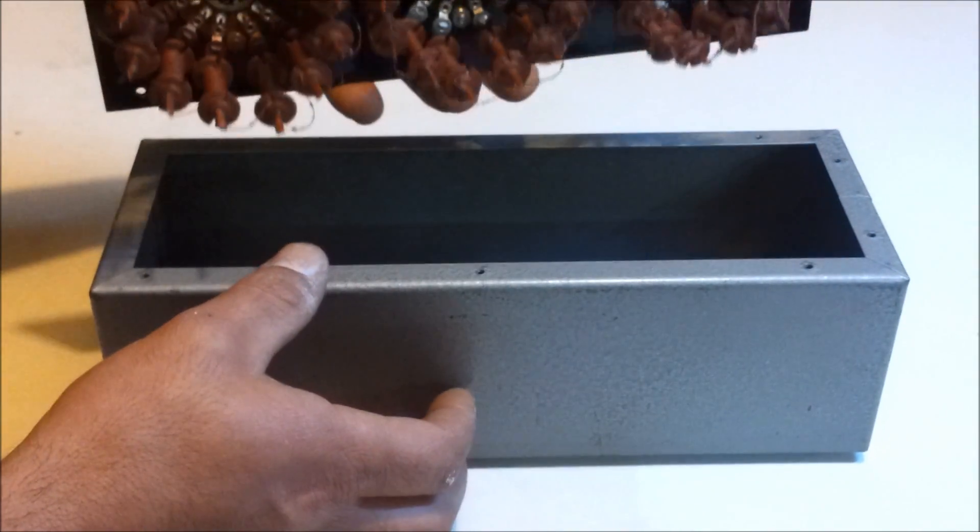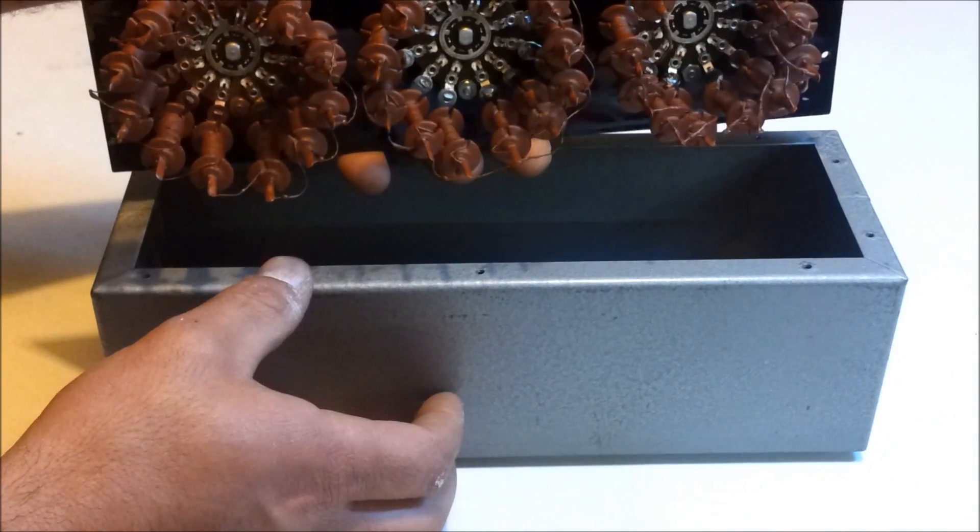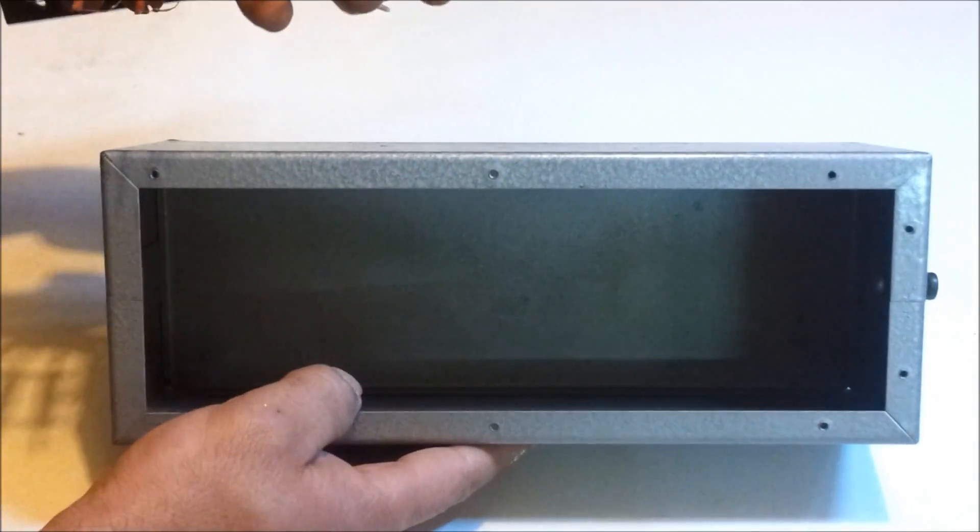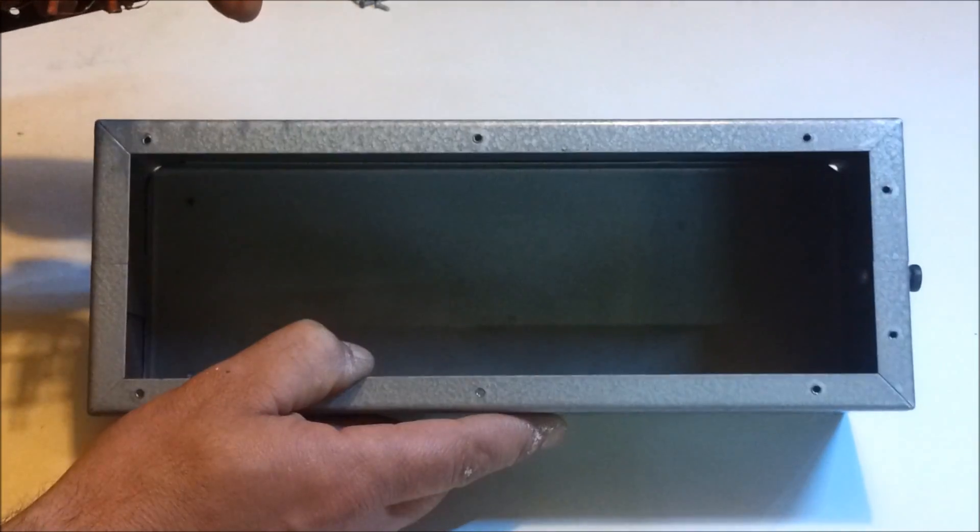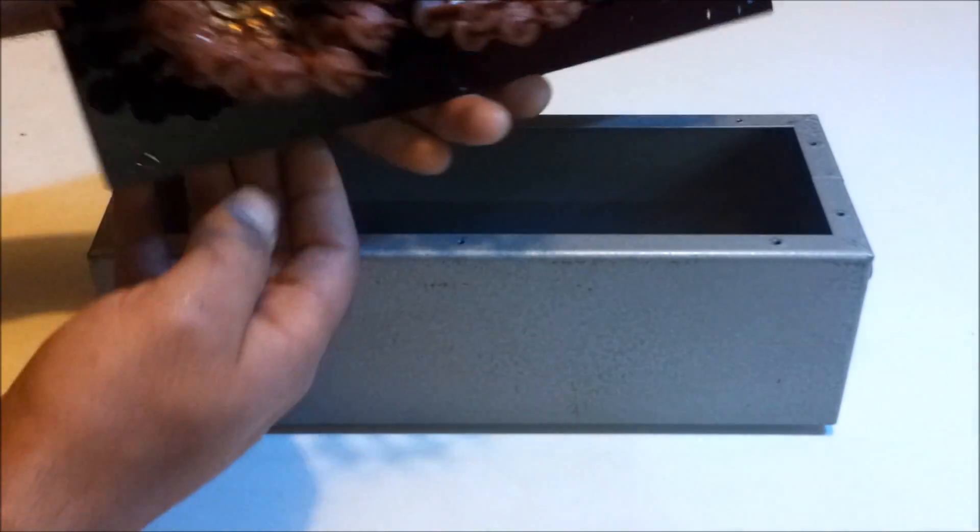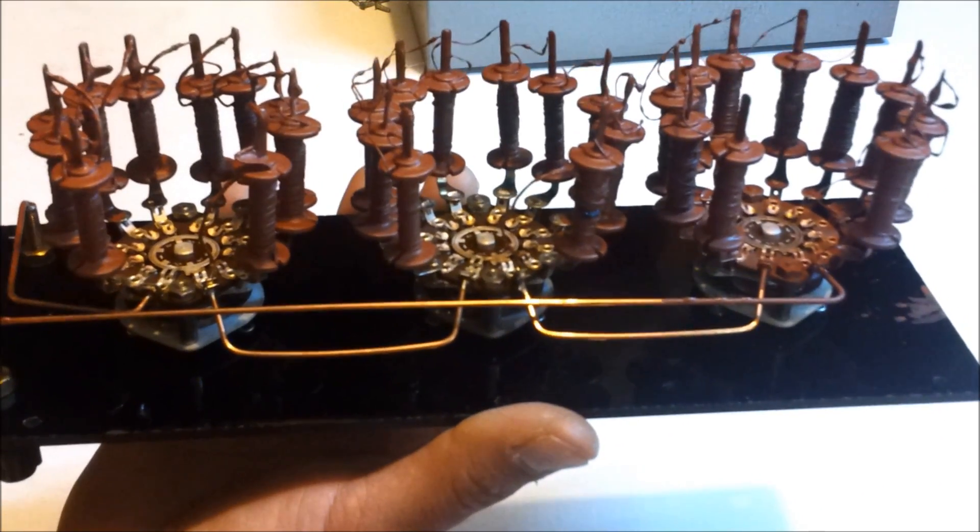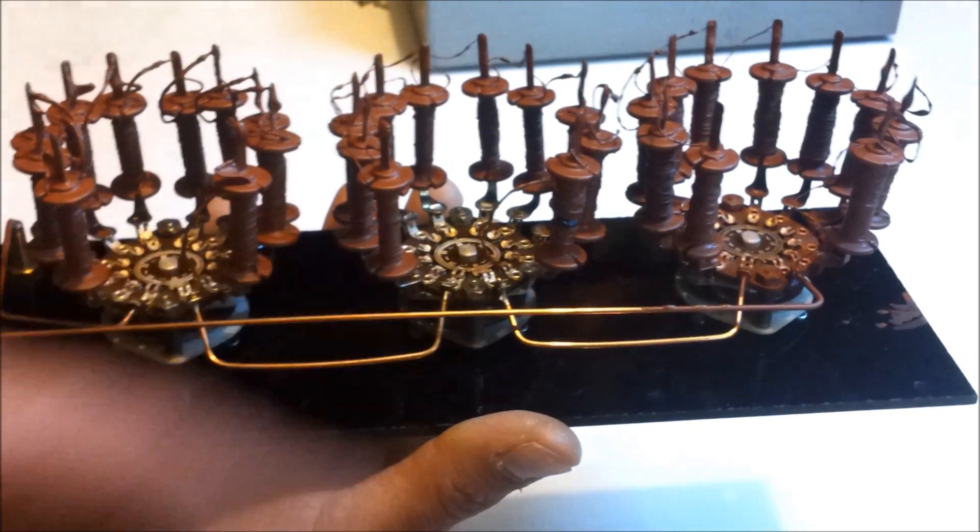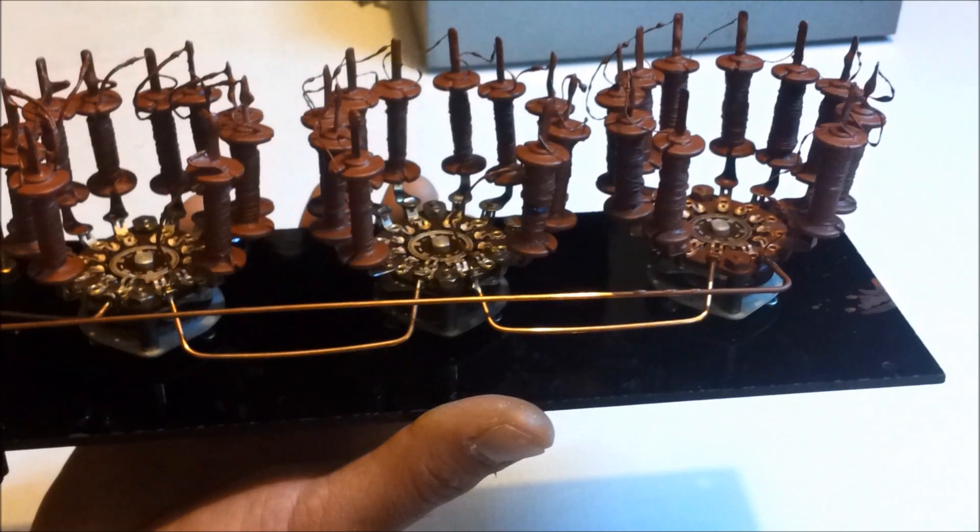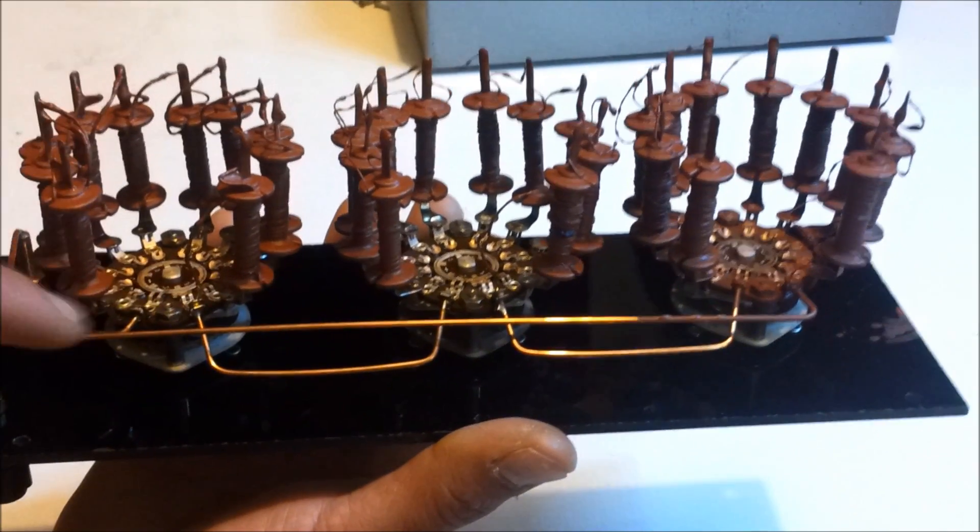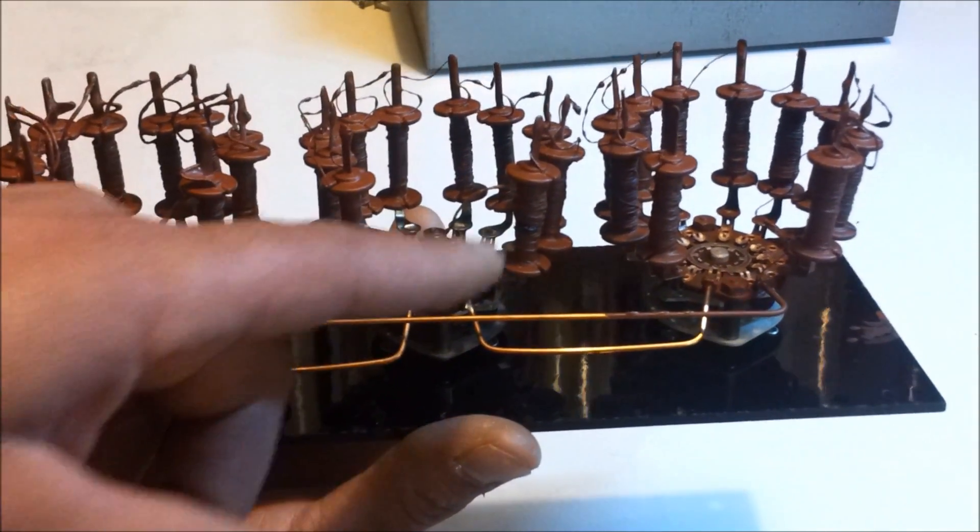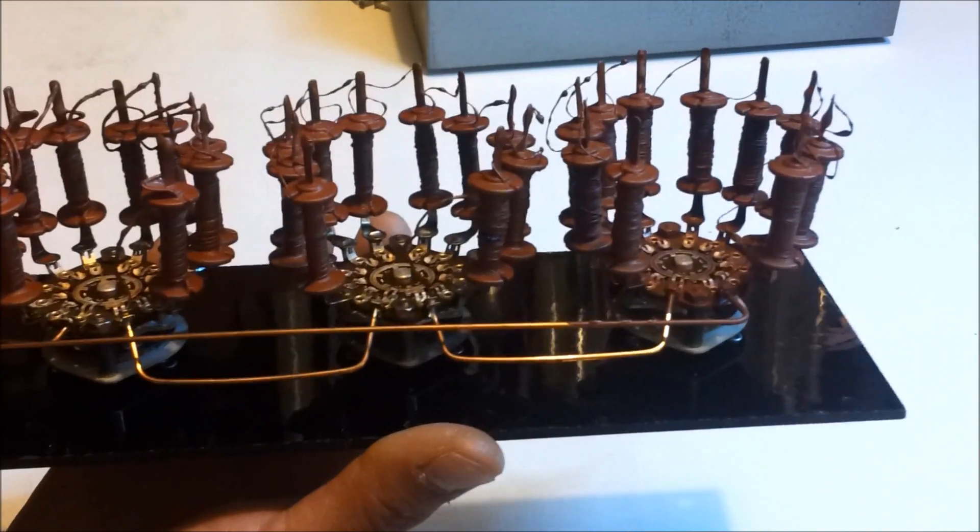That is pretty funky, pretty old-school looking. As you can see, the inside of the box is just a bit of folded steel, but this is where all the magic happens. We've got these solid copper bars here connecting the rotary switches together, and each one just contains wire wound resistors here and they've all been coated with some sort of coating.